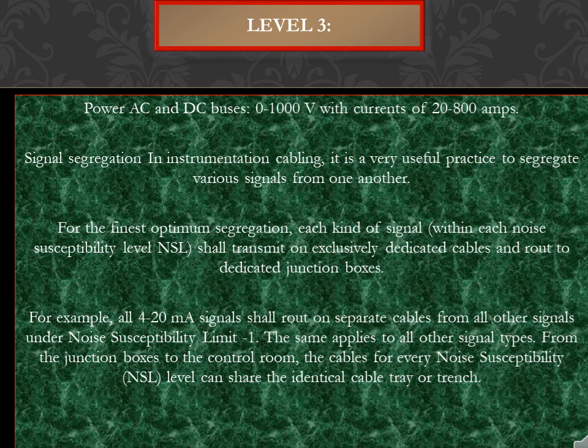Level 3 covers power AC and DC buses of 0 to 1000V with currents of 20 to 800 amps. Signal segregation in instrumentation cabling is a very useful practice. It is best practice to segregate various signals from one another. For optimum segregation, each kind of signal within each noise susceptibility level (NSL) should be kept as a separate carrier.